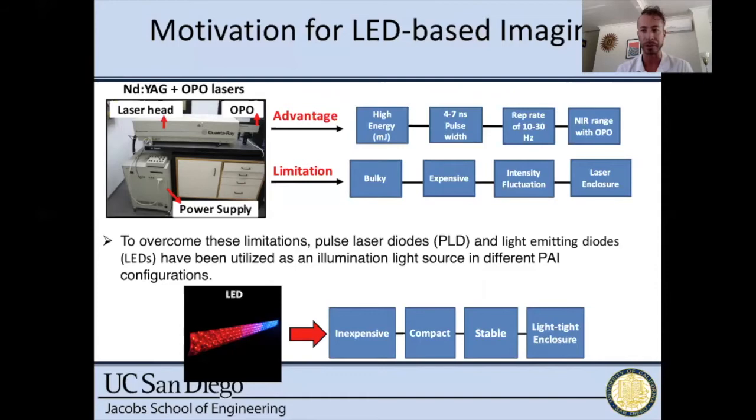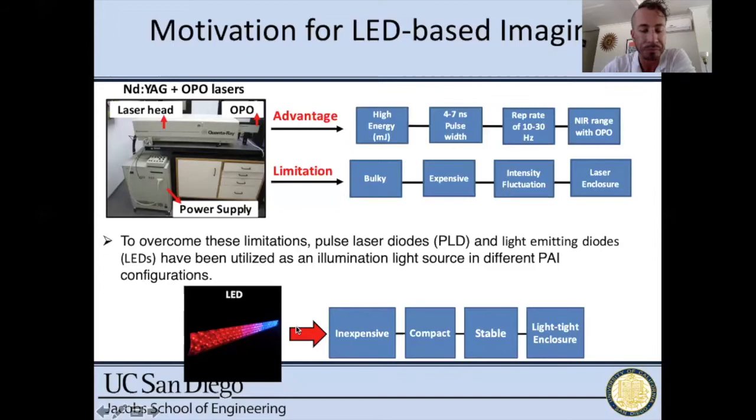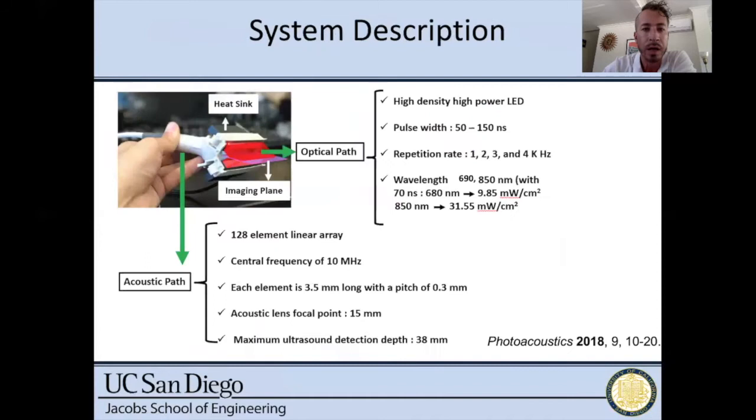The community has largely been using OPO tunable lasers. The advantages are high energy pulses, short laser pulses, and fairly good rep rates. The limitation is that they're very delicate, very expensive, very bulky, and require a lot of maintenance. As the field has moved more toward pulsed laser diodes and light-emitting diodes, I've been a real advocate for these because LEDs are inexpensive, compact, and stable. Our medical collaborators don't have time to fine-tune or babysit a laser — they need a light source that is always on and always works with little or no maintenance, and that's what LEDs offer.